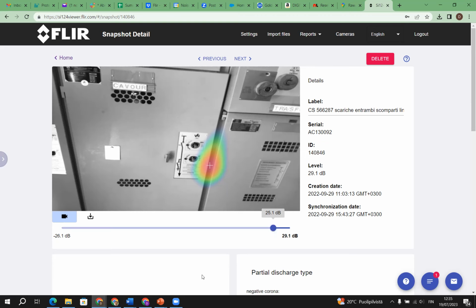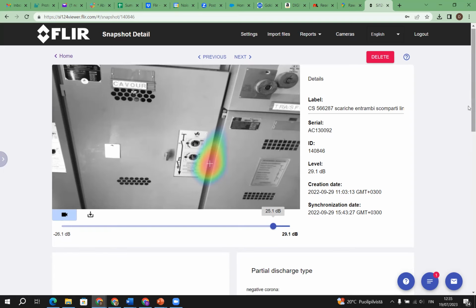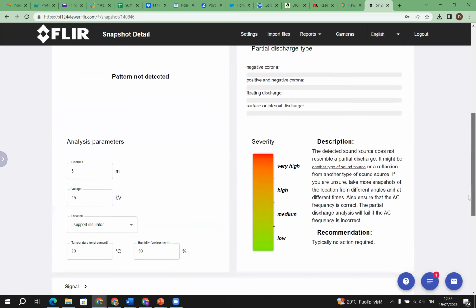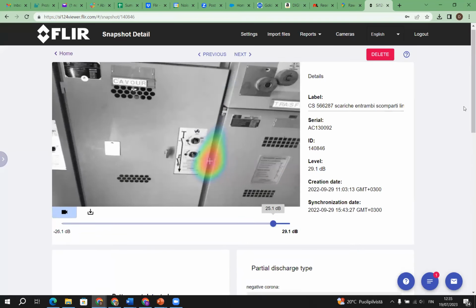That's why the camera is picking it up there. Of course, if you're able to open the cabinet - we weren't able to in this case because they said it's not safe - you'd be able to find what kind of partial discharge it is. In this case there's no analytics because it's not a direct interception, but at least you know there's something that you'll need to check at some point.